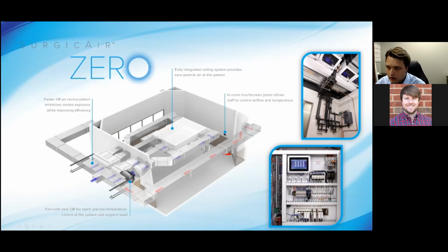What we're doing here is actually tripling the amount of air that's going into the room, tripling or 4 times the amount of air that's going into the room. So we're delivering air through a HEPA filtered array, and instead of sending all that air back to the hospital or to the air handler, we're actually taking most of it, bringing it through a pre-filter, and bringing it back to what we call a mixing plenum here. We're mixing this with the required air changes from outside per ASHRAE, reconditioning it, pressurizing it with the fans, and redelivering it back in through those HEPA filters into that room.